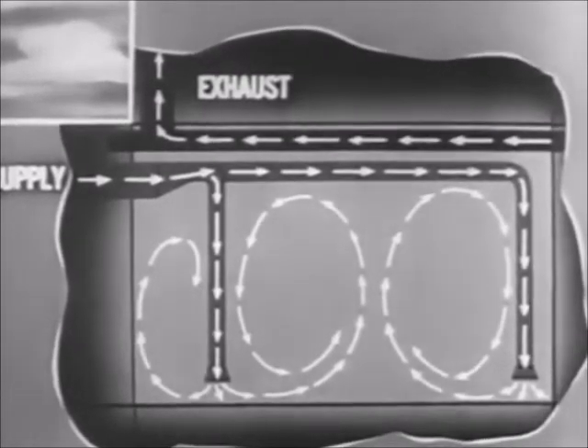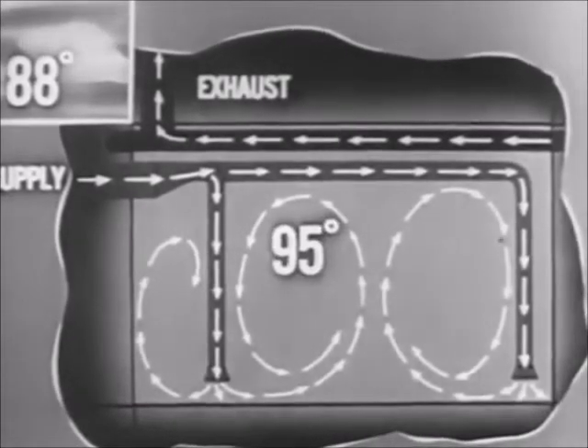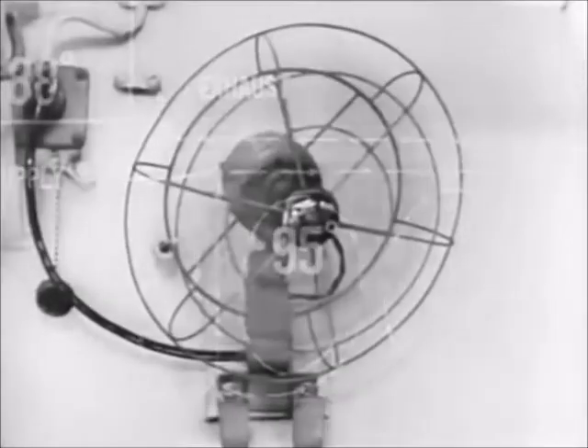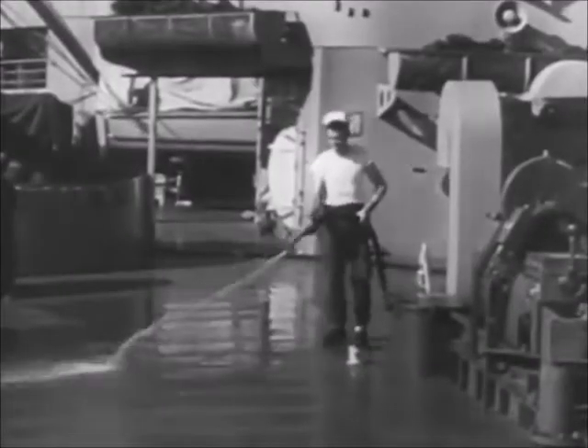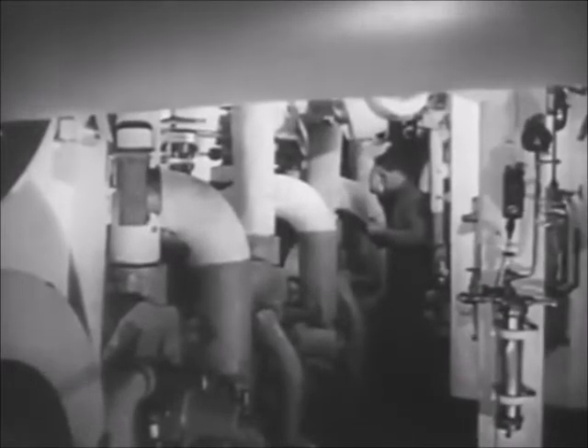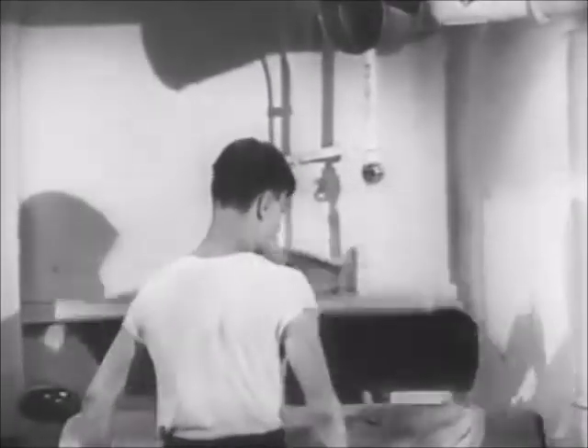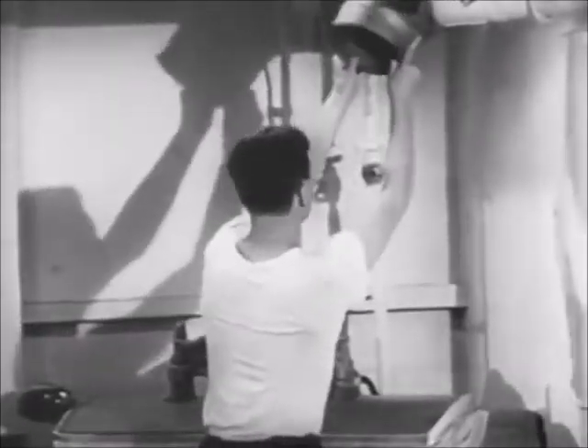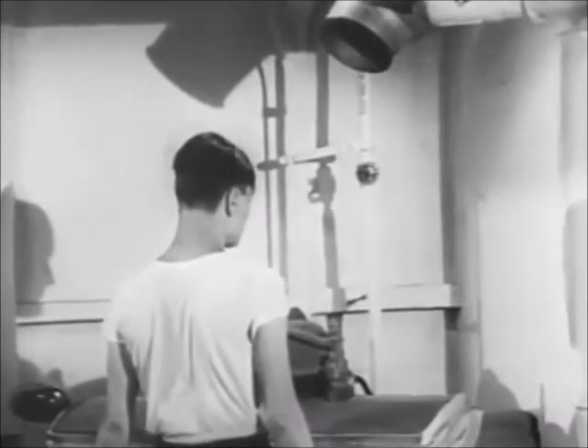If the temperature of the outside air is 88 degrees, the temperature in the berthing spaces should be no more than 95 degrees. Obviously, in extremely hot areas, ventilation air alone is inadequate. The installation of additional bracket fans will help, as well as frequent wetting of decks exposed to the sun. In very hot spaces, such as engine rooms, laundries, galleys, and pantries, it is not practical to maintain satisfactory temperatures throughout. So, a high-velocity blast of outside air is directed toward operating stations, creating an area of cooler turbulent air into which personnel can step for relief.